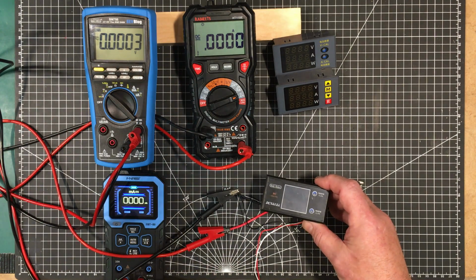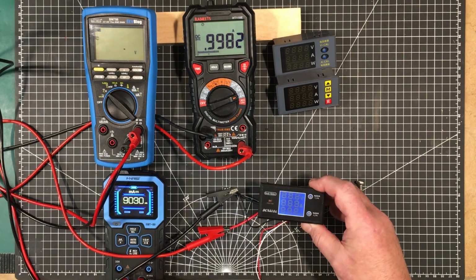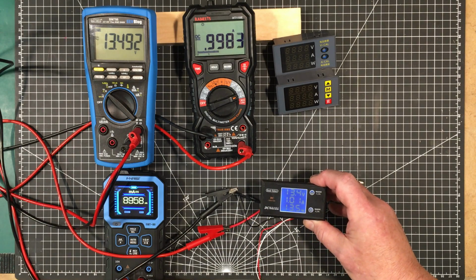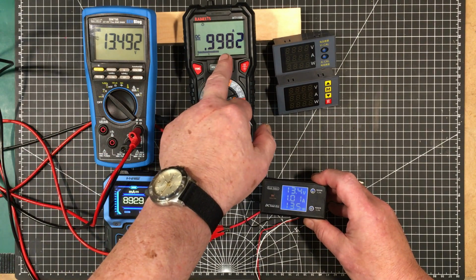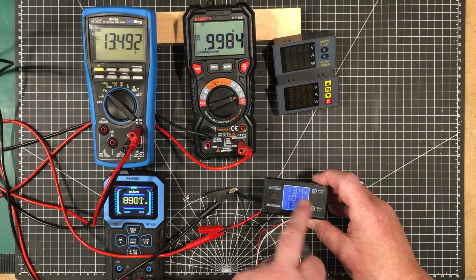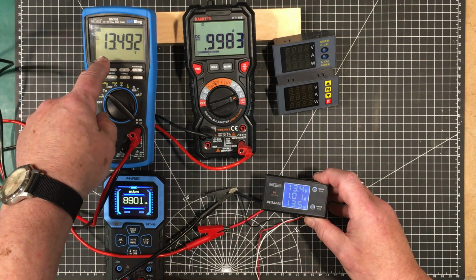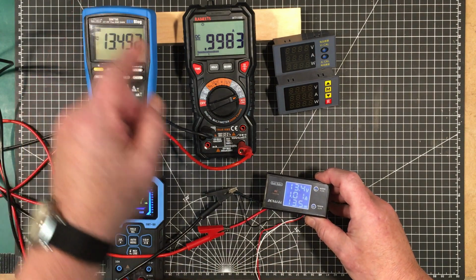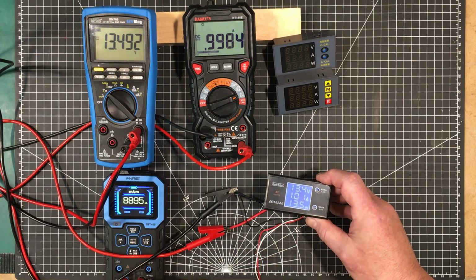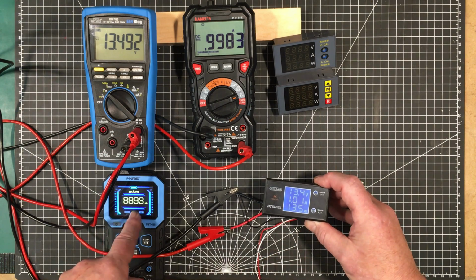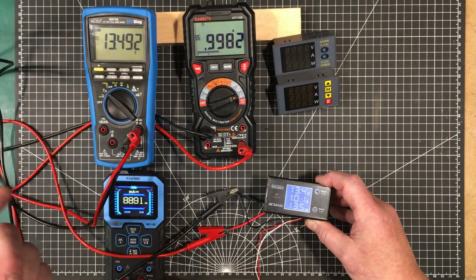Let's switch on the power. I've got the load set up right now for 1 amp, that should be good enough to test things out. We got 0.998, this is reading 1.01, so we could tweak that a little bit. The voltage here is 13.49, so this should be reading 13.5, and it looks like it's drawing approximately 8.9 milliamps.